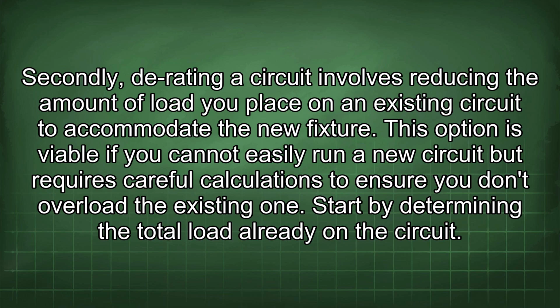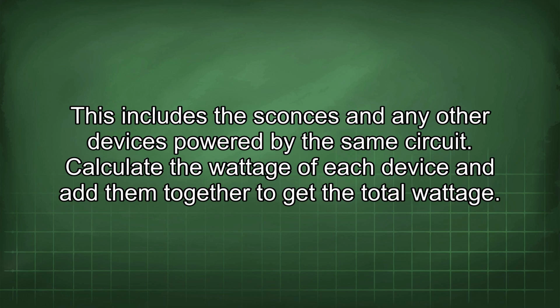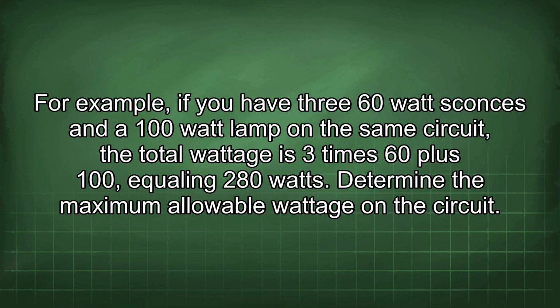Start by determining the total load already on the circuit. This includes the sconces and any other devices powered by the same circuit. Calculate the wattage of each device and add them together to get the total wattage. For example, if you have 3 60 watt sconces and a 100 watt lamp on the same circuit, the total wattage is 3 times 60 plus 100, equaling 280 watts.